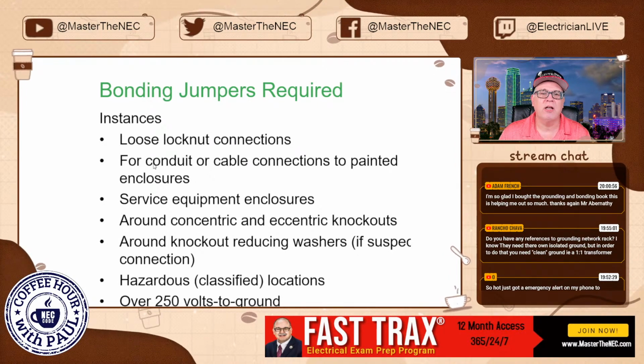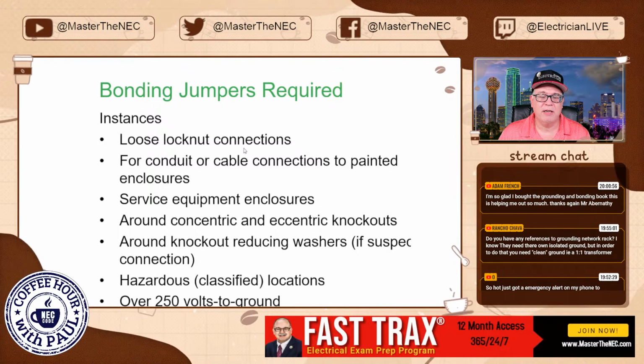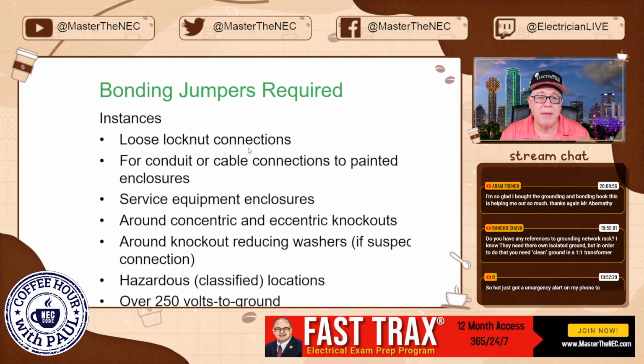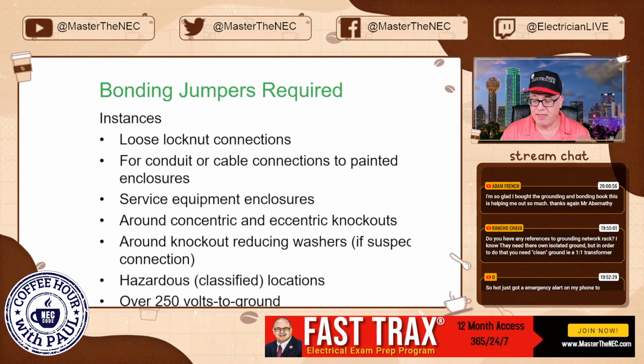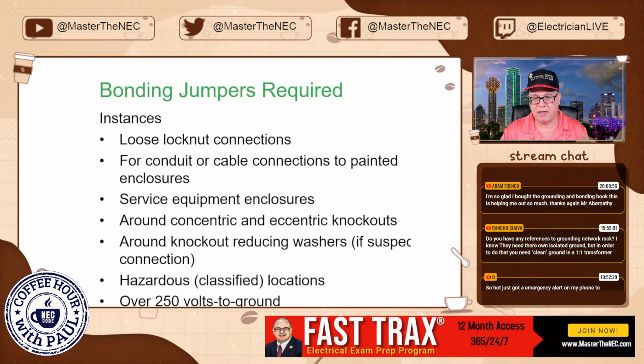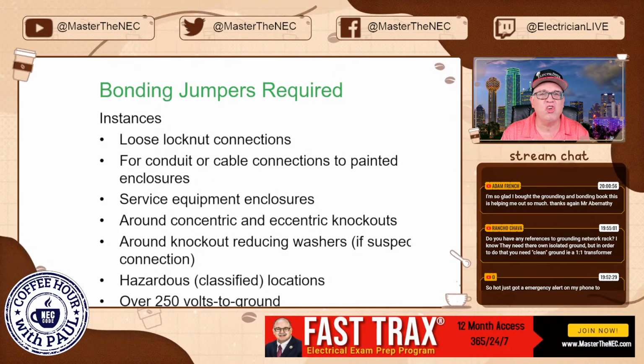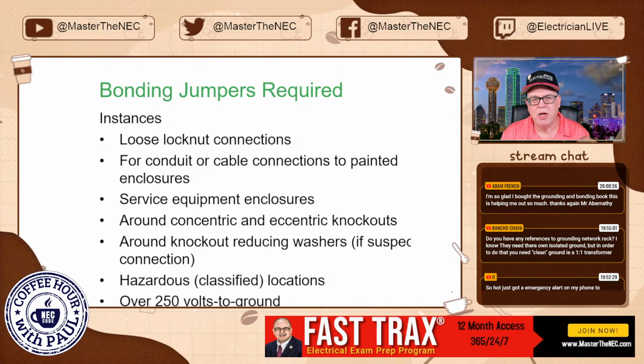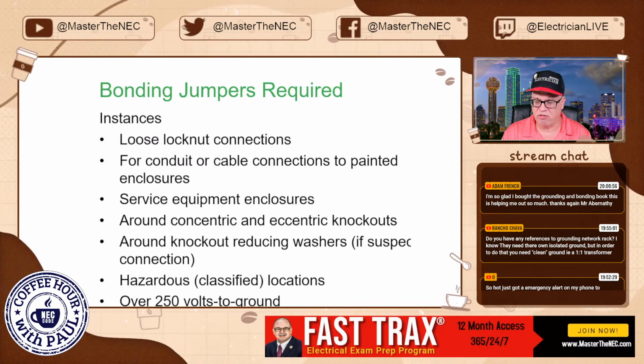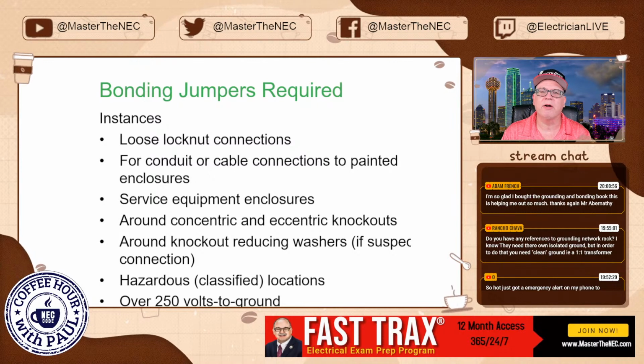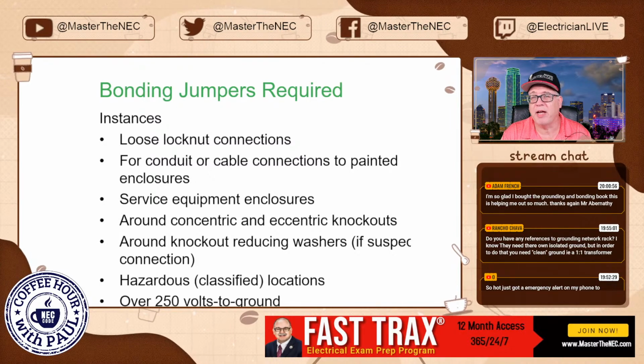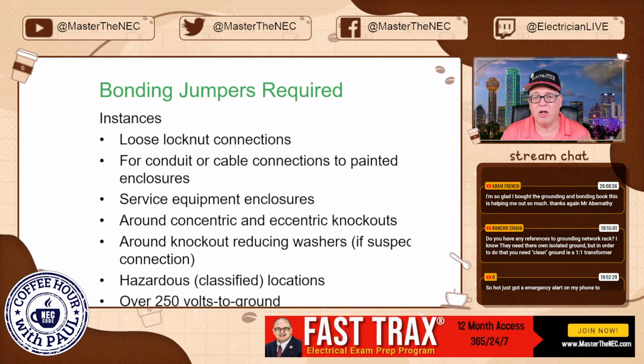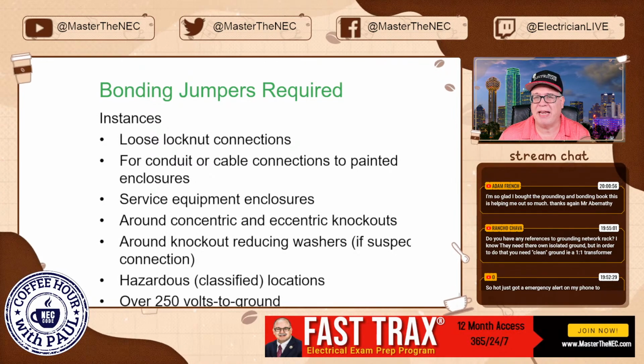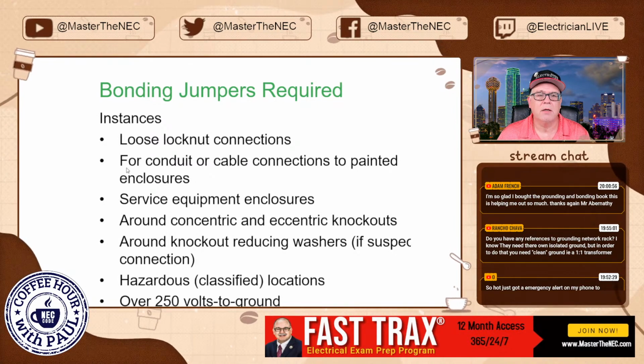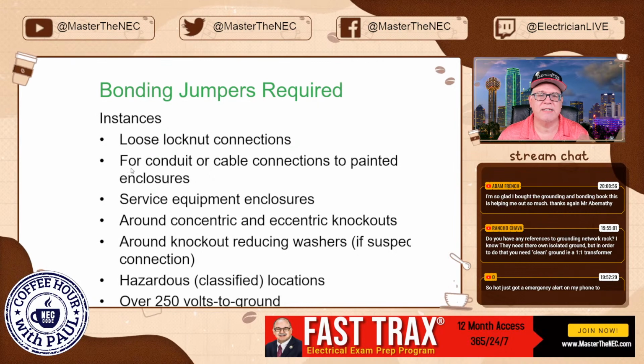And loose lock nut connections, okay? I don't know. If you're making connection with lock nut and the concentric, eccentric are so gnarly up, it's so knocked up, or the lock nut is so jacked up or whatever, then chances are you're going to need to put a bonding jumper on that. Another, because you cannot rely on the connection from that lock nut. Okay? That's very broad, but we'll go on and say that.